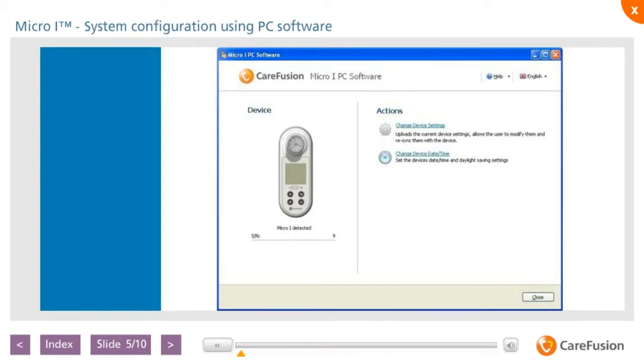Prior to using your Micro I, we also strongly recommend that the unit is configured to your own personal or practice spirometry requirements, including the language and indices you wish to measure. Customization can be performed either manually on the unit by selecting settings from the menu or through the PC configuration software. Insert the Micro I CD into a free drive on your PC and follow the installation instructions. When the software program is opened, the main window will provide options to configure the device or set the date and time on the unit.